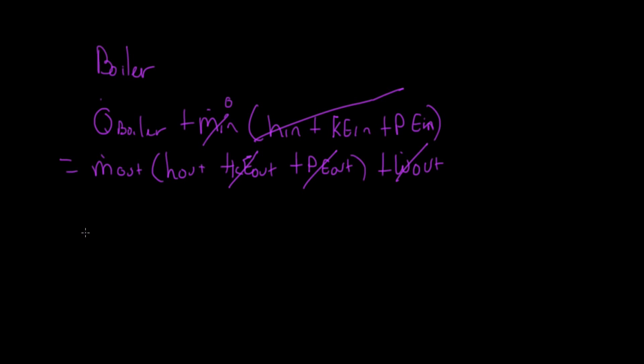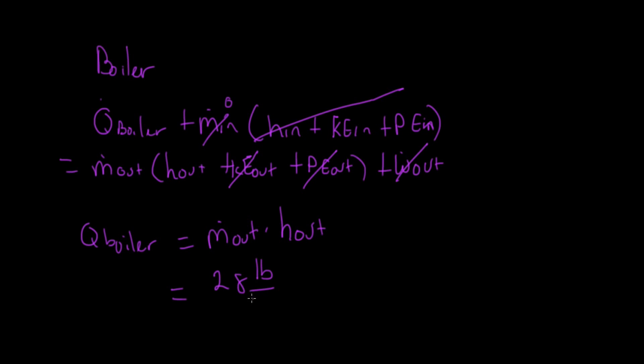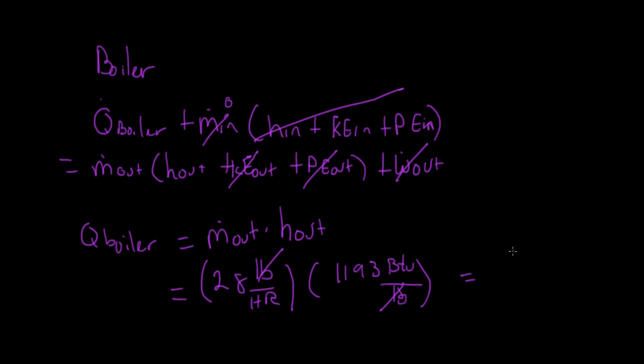This leaves us with Q_boiler equals mass flow rate out times H_out. From lab session three we have these two values, so let's plug those in: 28 pounds per hour times 1193 BTU per pound. The units cancel and we're left with Q_boiler equal to 33,404 BTU per hour.